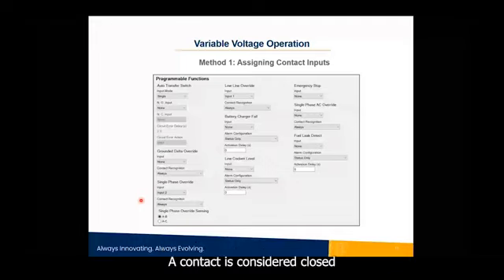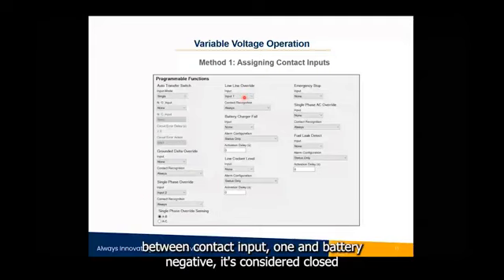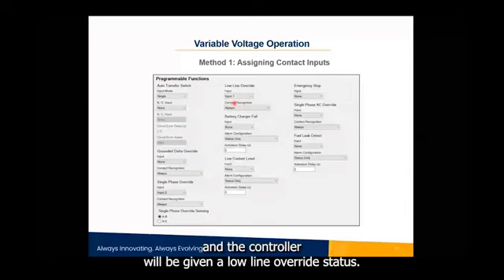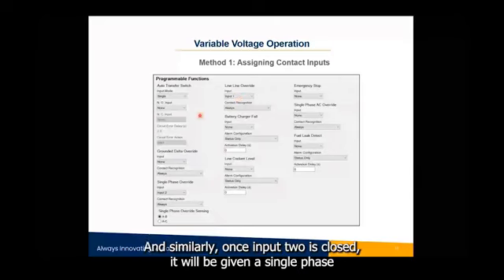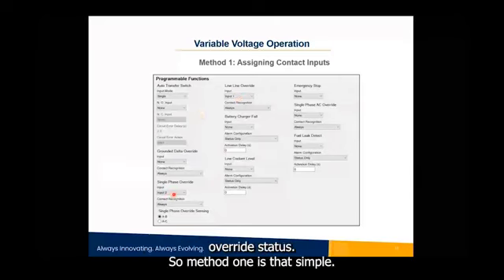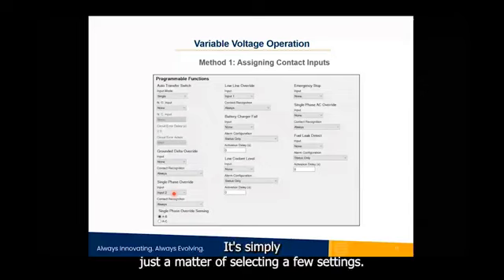A contact is considered closed when it is switched directly to battery negative. So as long as that direct contact is made between contact input one and battery negative, it's considered closed, and the controller will be given a low line override status. And similarly, once input two is closed, it will be given a single phase override status. So method one is that simple. It's simply just a matter of selecting a few settings.